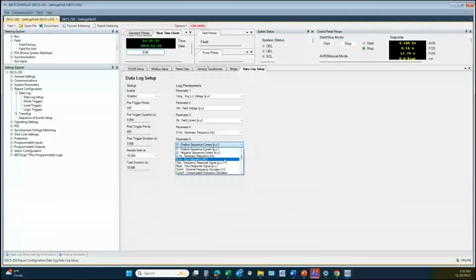And then a lot of times I'll recommend the control output within the list. As you can see, there's a long list of items available to have it record, but we can only record 6 different parameters. So the control output is what the DECS software is trying to do with field voltage. If there's a problem with the power input and the DECS is trying to drive field voltage up, but there is no field voltage being produced, it would let you know, hey, there's a problem with most likely the power input voltage.